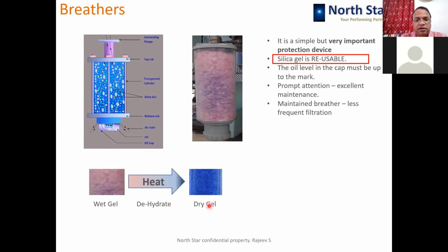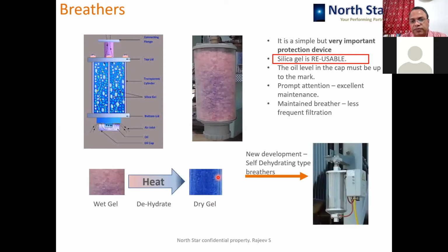So you can dry the gel by simple heating and get it back. So it is very easy that way. Now to save the people even that much pain, self-dehydrating type of breathers are available, which have a heating element inside, operated by a microprocessor. It is a very sophisticated way to keep your silica gel dry, and that way this equipment is very effective in protecting the transformers from external moisture. Internal moisture, of course, would be there, but the external moisture impact can be saved by this.